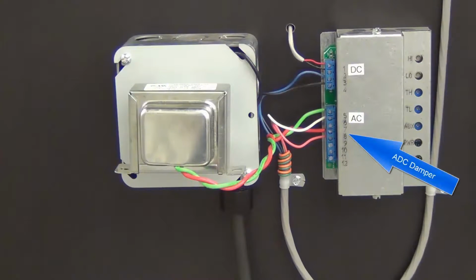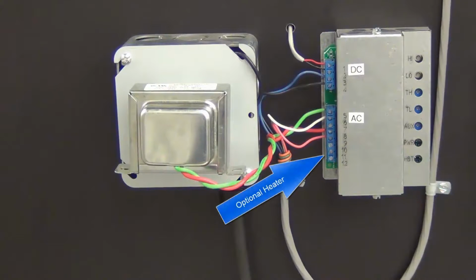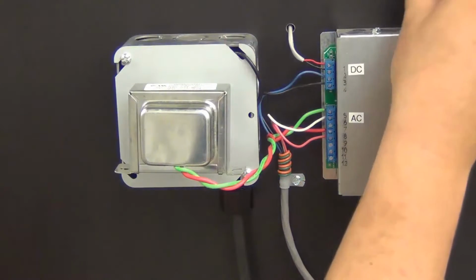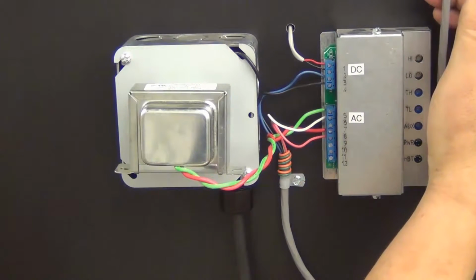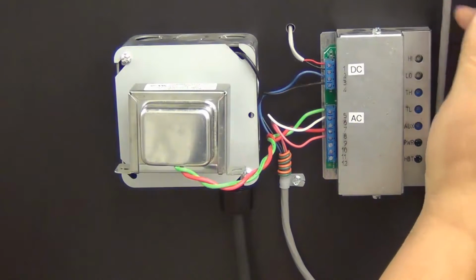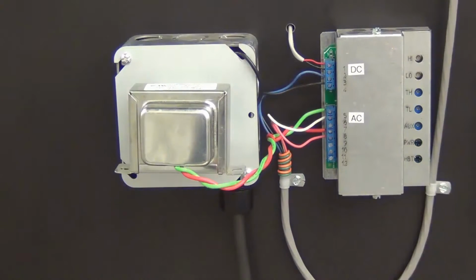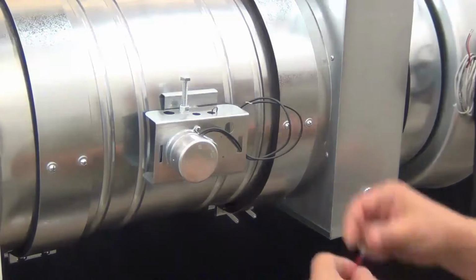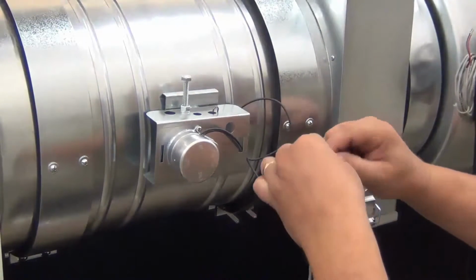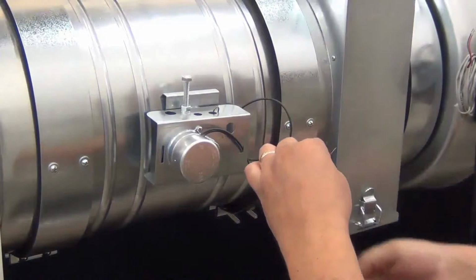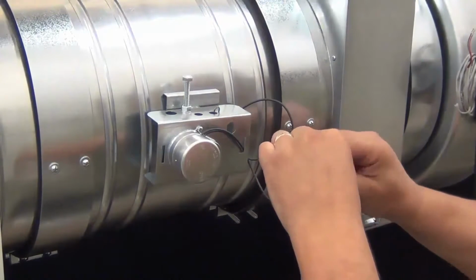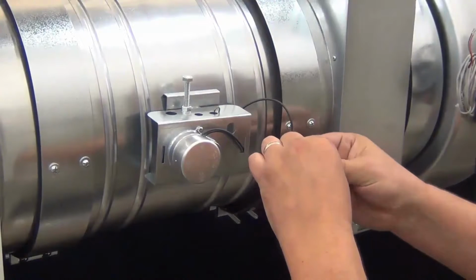Terminals 6 and 8 are for the low voltage connection to the ADC shut-off damper. Terminals 9 and 10 can be for an optional heater. This is the low voltage going to the Makeup Air fan, Makeup Air damper and optional heater if installed. Connect the low voltage wire from the controller to the damper. Note, the connections are not polarity sensitive.